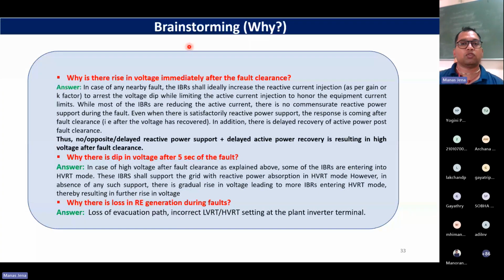Essentially, for the first question, this is the answer. Either there is no reactive power support, or opposite reactive power support, or delayed reactive power support, plus delayed clearance and delayed active power recovery, is actually what is contributing to the over voltage. Once there is over voltage, what happened? Many transmission lines also tripped for that particular event.